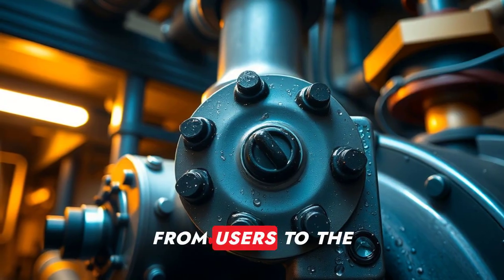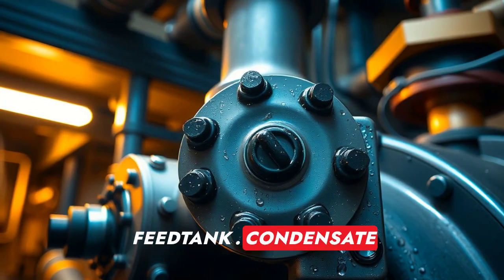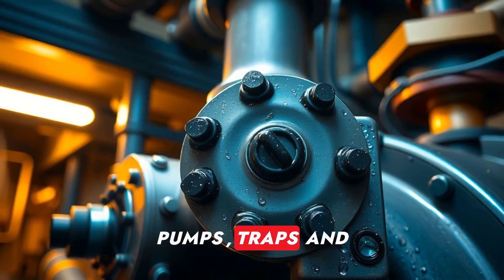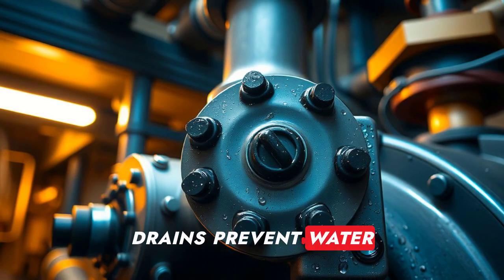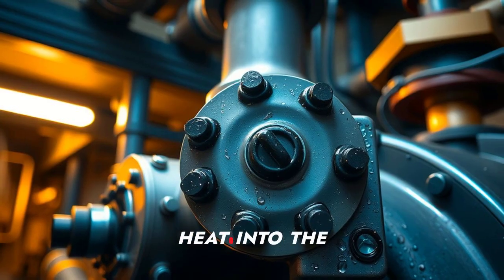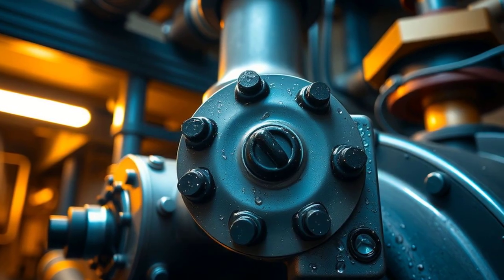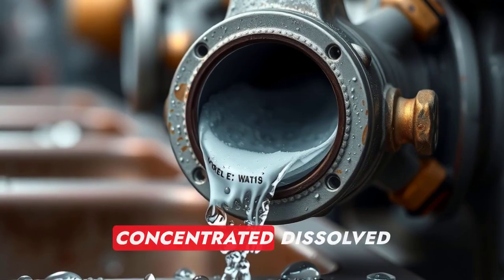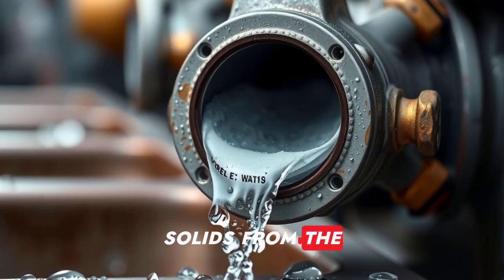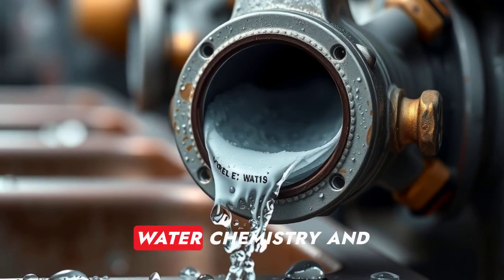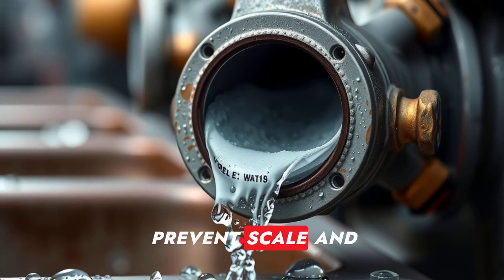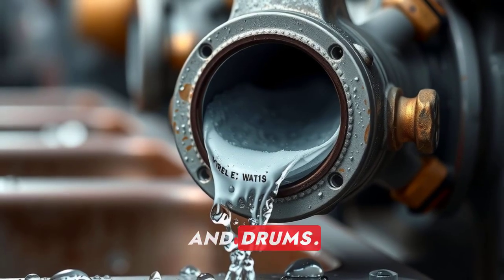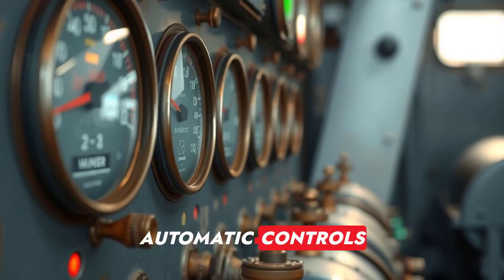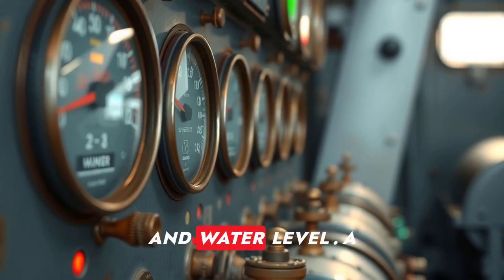Condensate returns from users to the feed tank. Condensate pumps, traps, and drains prevent water hammer and recover heat into the feed water system. Blowdown removes concentrated dissolved solids from the boiler to control water chemistry and prevent scale and corrosion in tubes and drums. Automatic controls regulate pressure and water level.